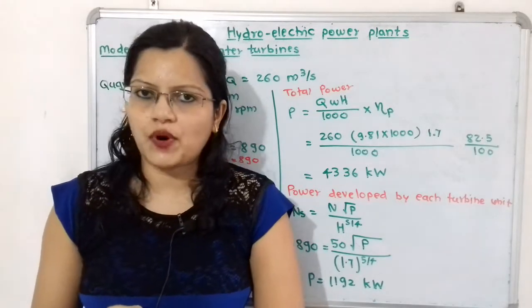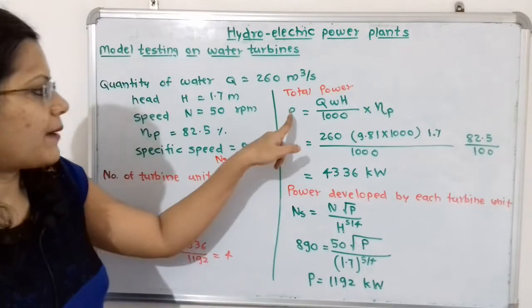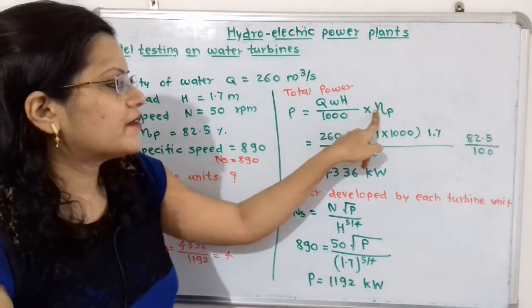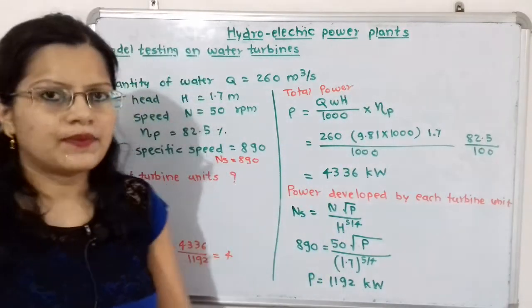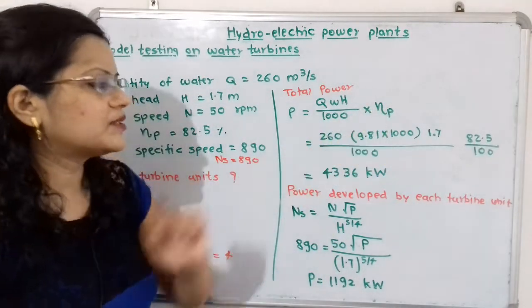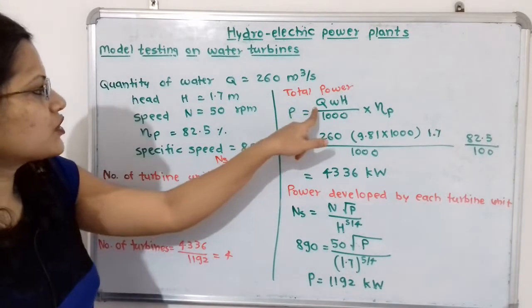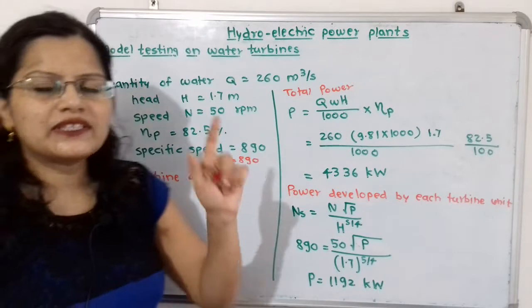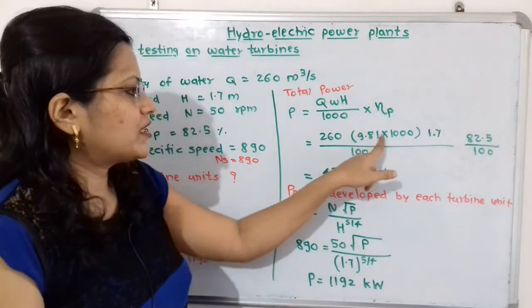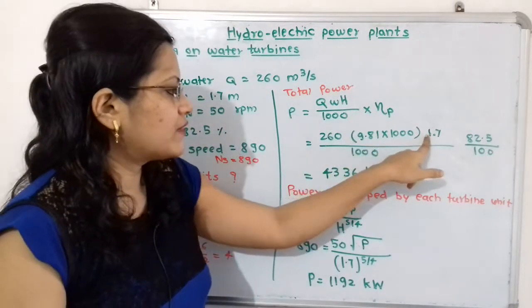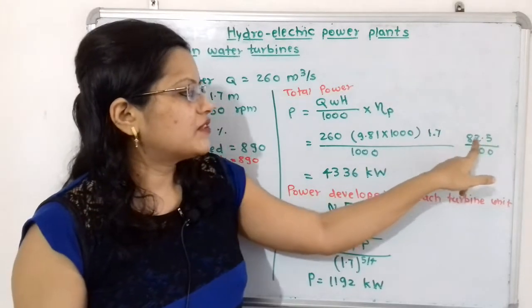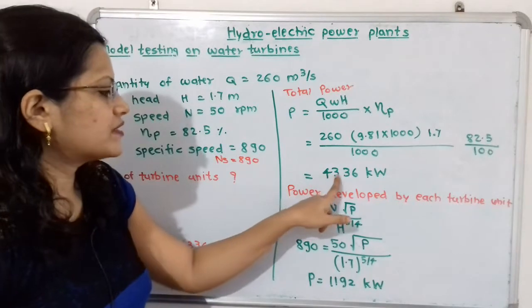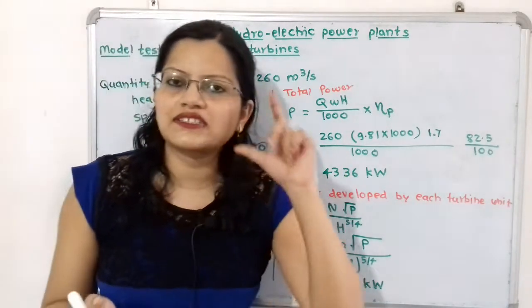To calculate the total power, the formula is P = Q × W × H / 1000 × efficiency of the prototype. Here Q is 260, W (water density) is 9810 N/m³, H is 1.7 meters, divided by 1000, multiplied by efficiency 82.5 divided by 100. This gives a total power equal to 4336 kilowatts.